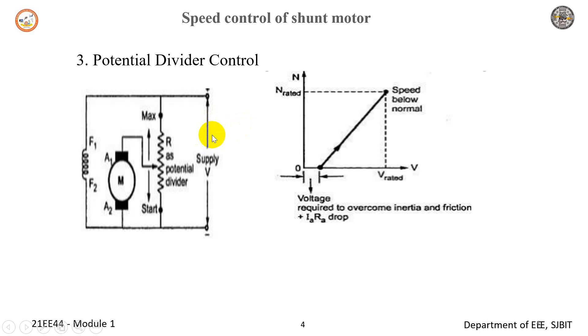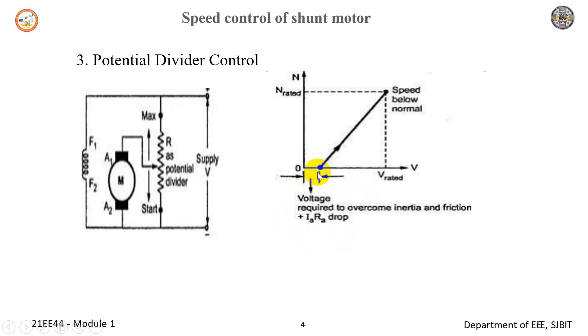Speed down to 0 is not possible in the previous method because we would need to insert a larger rheostat in series with the armature, which is practically impossible. If speed control from 0 to rated speed is required, then we need to employ this potential divider arrangement as shown in the figure. The voltage across the armature can be varied by varying this potential divider resistance. When the voltage across the armature starts increasing, as long as the motor does not overcome the inertia and frictional torque, the speed of the motor remains 0. Once it overcomes this drop, the motor starts. Hence the graph of voltage versus rated speed does not pass through the origin, because some voltage is used to overcome inertia and friction.